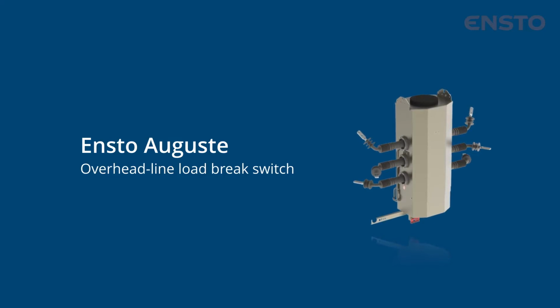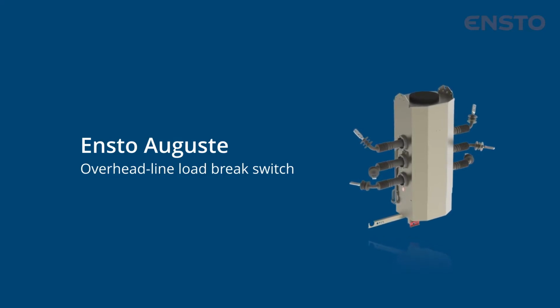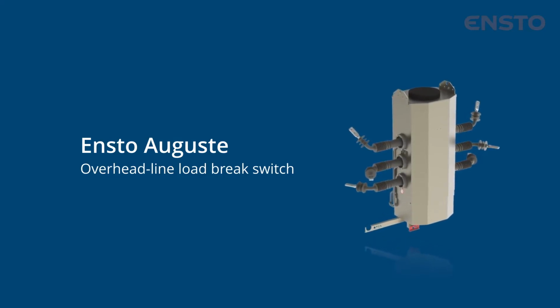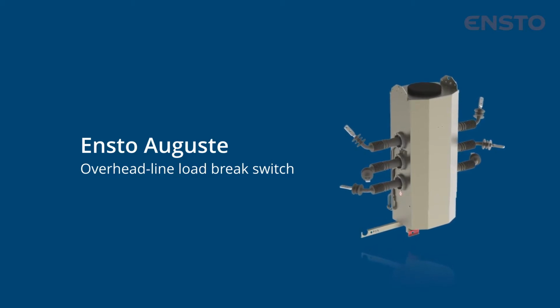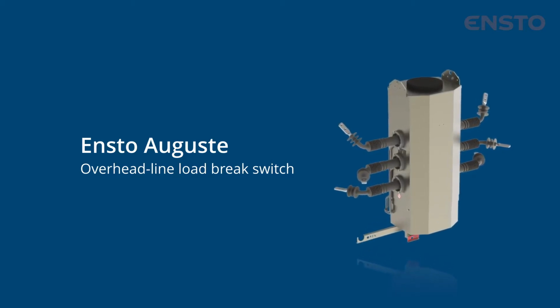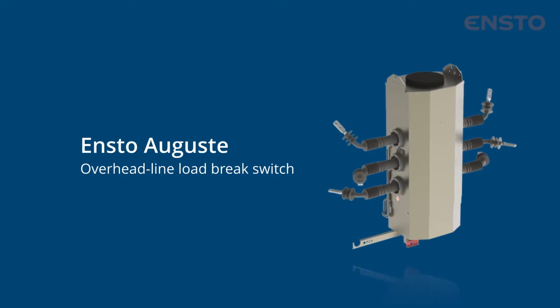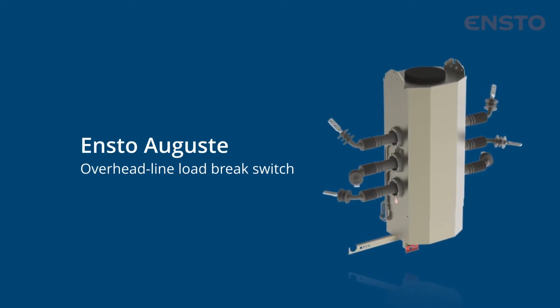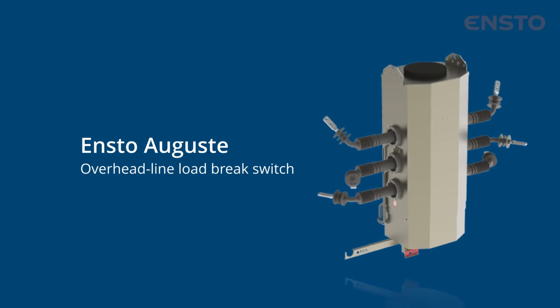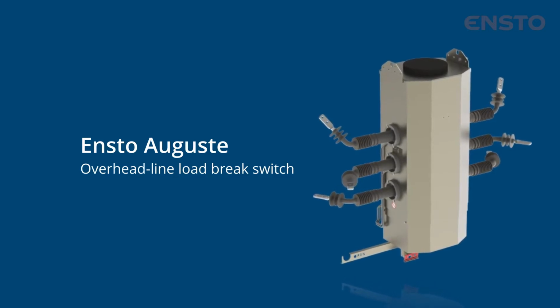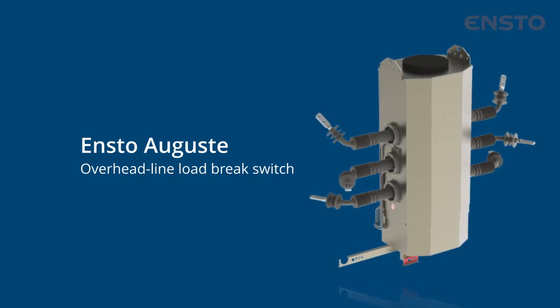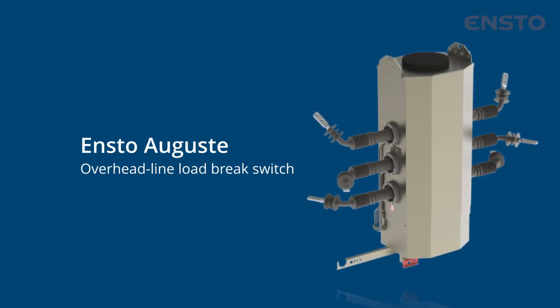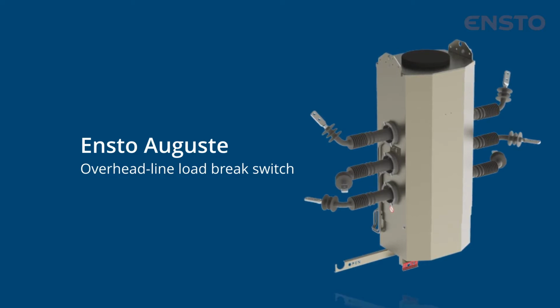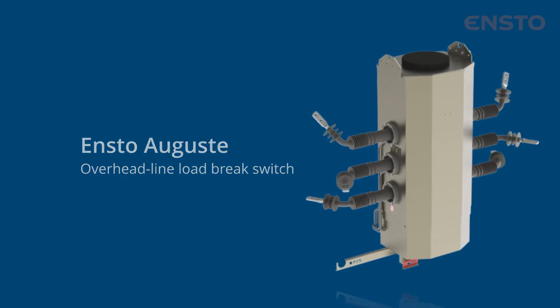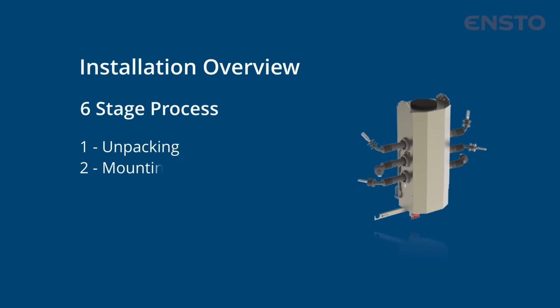It is recommended to check the unit supplied matches the specification and is suitable for the network location and operating voltage before commencing installation. The switch in this demonstration is equipped with external bushings with 2-hole connection lugs and has an internal voltage transformer to power the unit at low voltage. This Auguste is equipped for hook-stick manual operation, as well as remote control, which can be directed to the host DNO SCADA system. Now we carry out the 6-stage installation process.